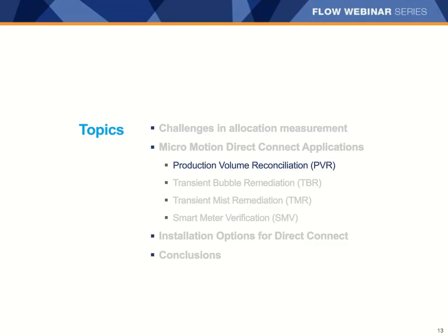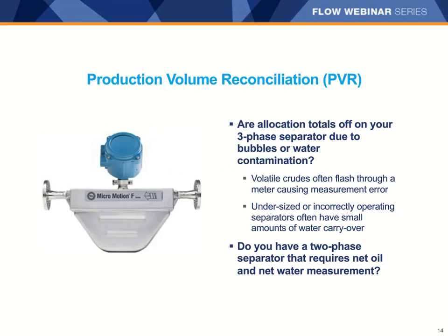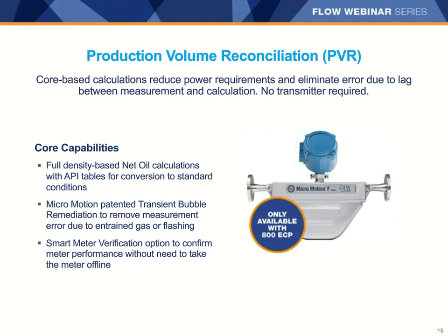PVR is ideal if you have challenges with volatile fluids off your three-phase separator or have carryover of water in your oil leg. Or if you have a two-phase separator, PVR will help you distinguish between the oil and the water going through your meter, giving you net oil, net water, but still subtracting out any volume attributable to bubbles. PVR has full density-based net oil computing coupled with the ability to remediate for bubbles.